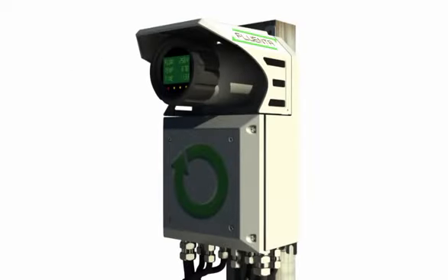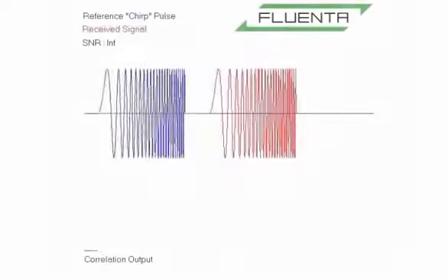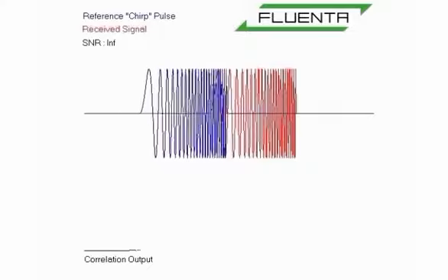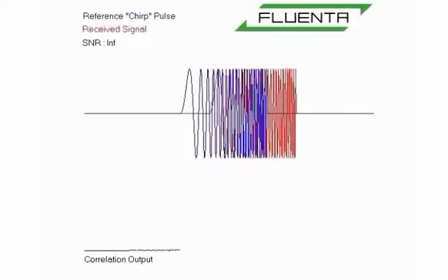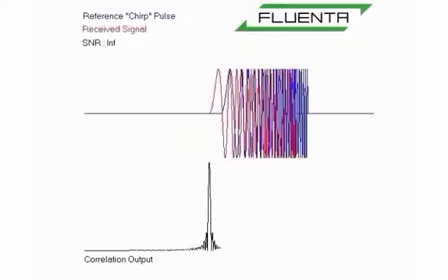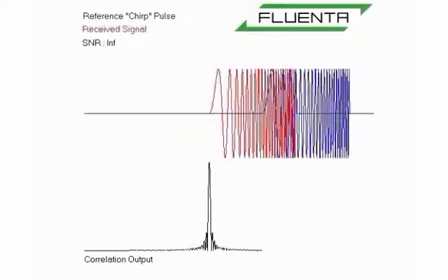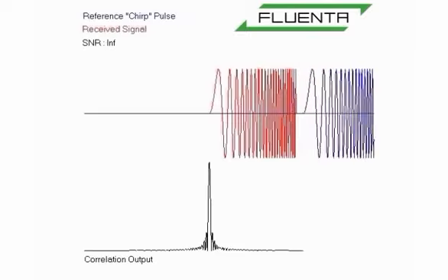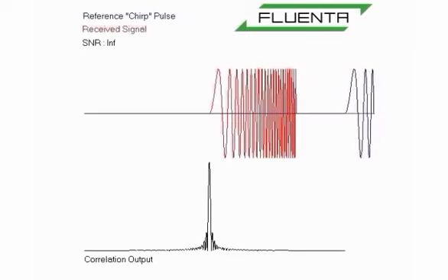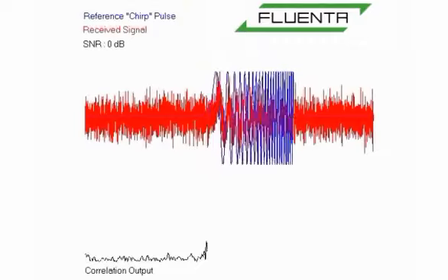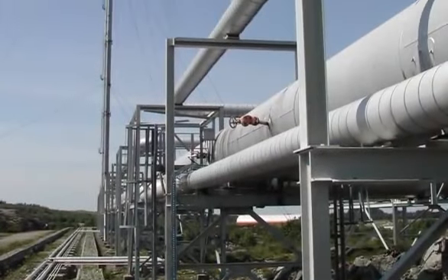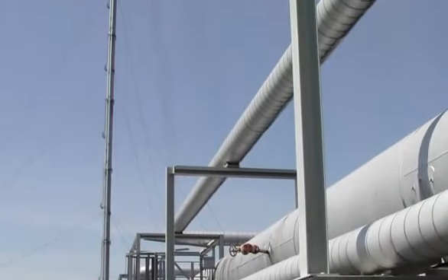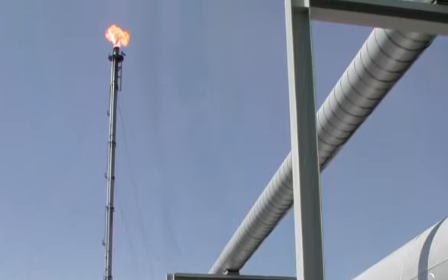Due to the unique chirp signal processing capability in the Fluenta flare gas meter, it can measure higher flow rates than any other ultrasonic flare gas meter. This technique detects exactly when the signal is received for both sensors. The electronics sort out the signals which reach the set acceptance level and calculate the flow and the density based on this. And such is its accuracy that the Fluenta flare gas meter is used by all major Norwegian oil and gas companies to help calculate taxes payable on CO2 emissions.